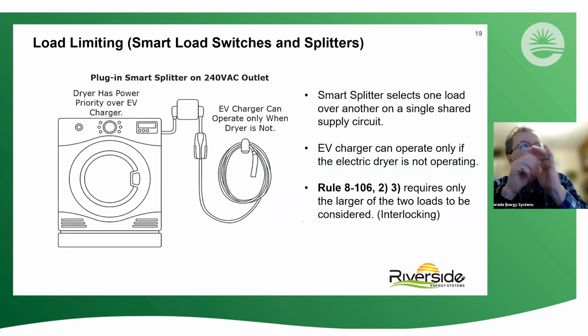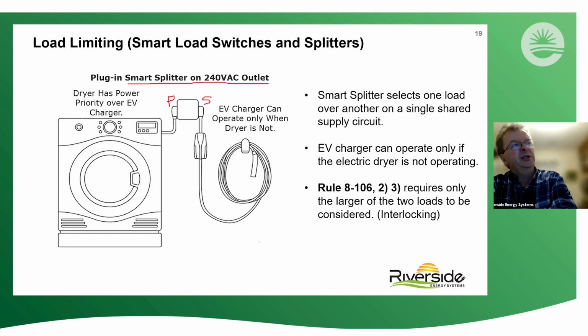Other strategies with interlocking, Rule 8-106, 2 and 3, we can install smart splitters. This is an example of a plug-in one, but you can also get hardwired ones. And these smart splitters mediate the use of the circuit between two loads. So in this case, the dryer has primary priority and the EV charger has standby priority, so that the EV charger could only operate if the dryer is not operating. So this is the kind of logical switching we can use to again control our demand.